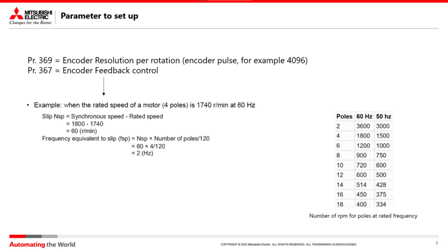Parameter 367 is the encoder feedback control. This value is obtained from a calculation: slip multiplied by the number of poles, with the whole divided by 120.